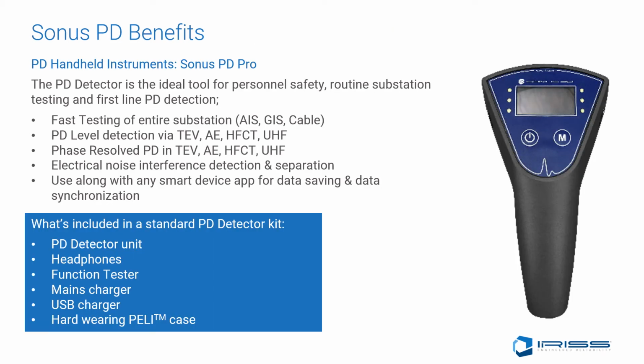The Sonus PD Pro is the PD detector that is an ideal tool for personal safety, routine substation testing, and first-line PD detection. Its fast testing of the entire substation allows for the testing of AIS and GIS as well as cabling. The PD level detection with TEV, ultrasound, HFCT, and UHF gives the inspector the confidence that they're able to determine what is occurring. The phase resolved PD in TEV, AE, HFCT, and UHF also allows the inspector another view and dimension of what is occurring on their screen. Electrical noise interference again is detected and separated from the actual display of the intensity of the anomaly.